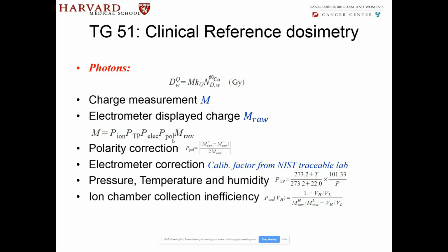So you would take one measurement at, say, 300 volts, and the next one we usually do at 150 volts. We have the voltage VL, the low voltage, and VH, the high voltage. Take the different voltages, do the measurements for the charge, M raw H and M raw L, corresponding to high and low voltages, and then apply this. Again, this has to be very close to 1. If it is more than 5%, don't use your ion chamber. There's something wrong either with the ion chamber or the electrometer.